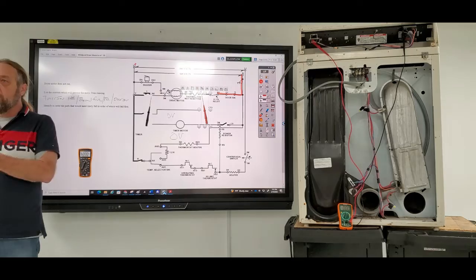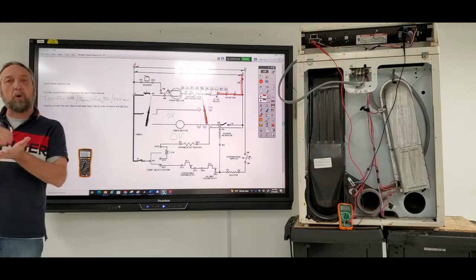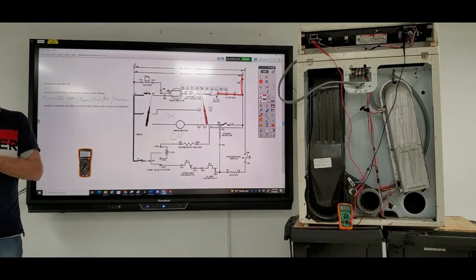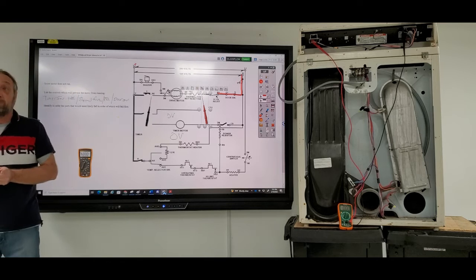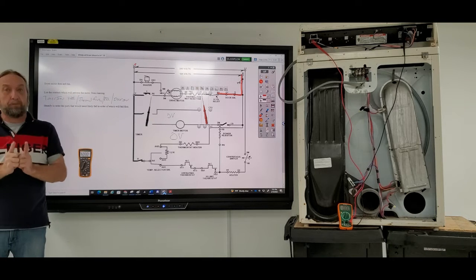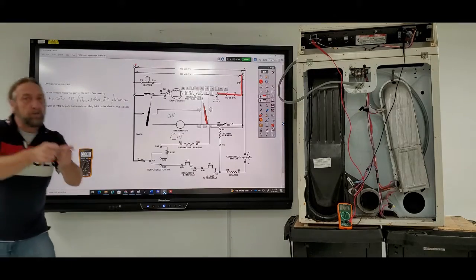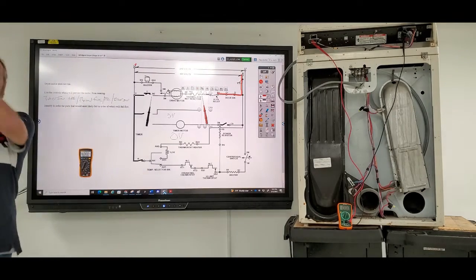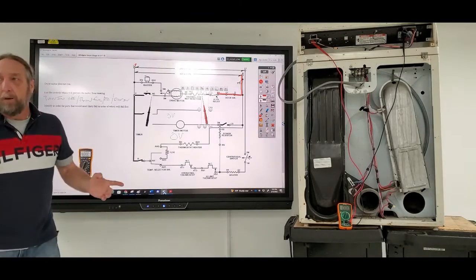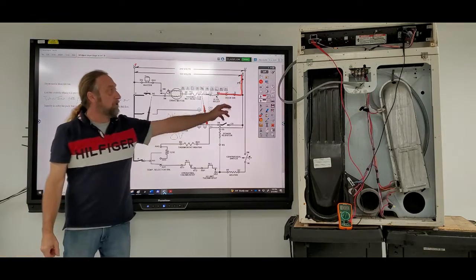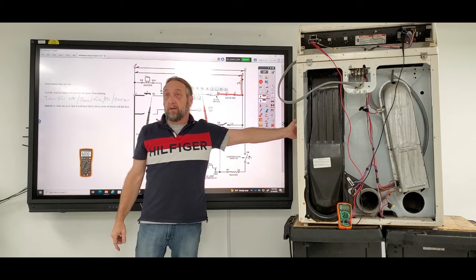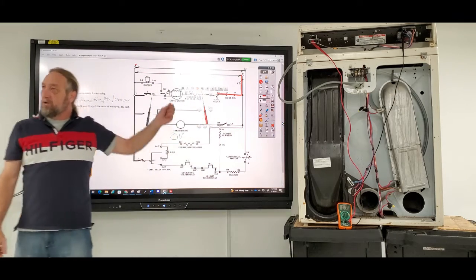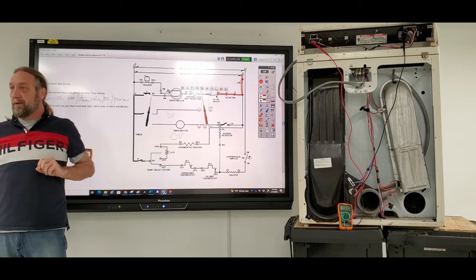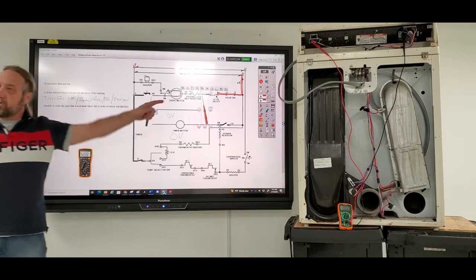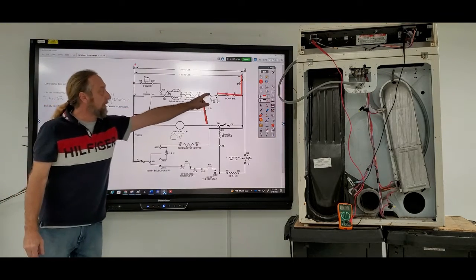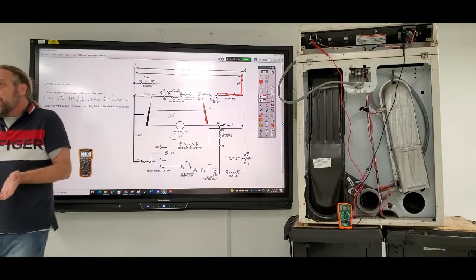Yes, we can check each component, but not only checking components, we're also checking all the interconnecting wires. We're checking an entire circuit with voltage. We're not checking one part with voltage. When we do ohms, we're only checking one part, and we're jumping all over the machine checking one part, but one part, like this door switch, is in front of the machine. And if I have voltage at the start switch right now, the way it's wired in the diagram, I know my door switch is good because I have voltage to this point here. So I don't have to check the door switch.